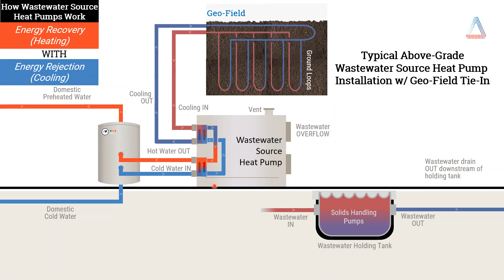And then utilizing the secondary source when it comes to that geothermal field and the secondary evaporator, we would tie in through a hydronic line to the geofield, and again draw energy out of that field when applicable, taking a load off of the field, using that energy as the source to output domestic hot water. So again, both of these types of systems can be used in tandem or independently, depending on demand and seasonality, in order to drive the overall efficiency and effectiveness of wastewater, geothermal source, and hot water output. So that covers the small scale energy recovery type of application.